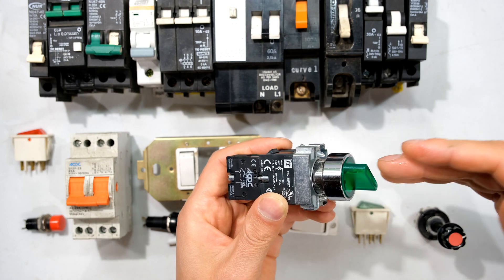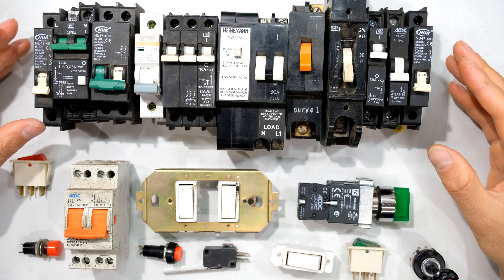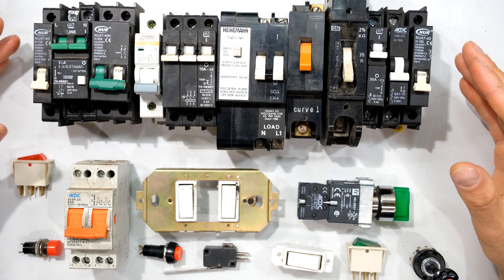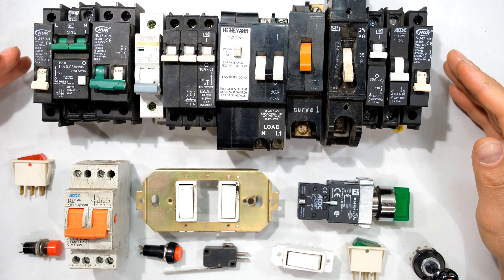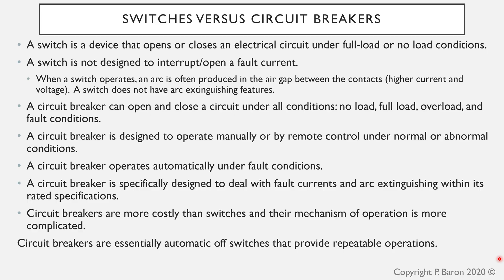A switch, on the other hand, has only manual operation. If the current exceeds a certain amount, all that will happen is the switch will burn out — it is unable to automatically open the circuit. Some circuit breakers can be remote controlled, meaning you can initiate a trip from a remote location. A circuit breaker is specifically designed to deal with fault currents and arc extinguishing within its rated specifications.